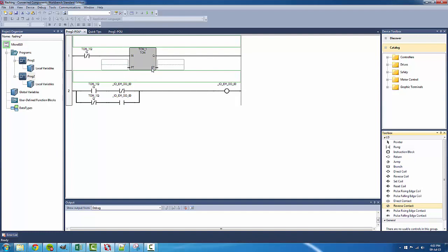So basically we've got TON over here. Let's just enter T#500ms. So it's going to count up 500ms, turn on, count up 500ms, turn off. Every time the timer is activated, this turns on for a split second because as soon as it turns on, it turns off again for a split second. When this turns on, if this is closed, then that will activate. When that activates, it's going to activate this. Since this goes back into its original position after a split second, it's going to be latched on.